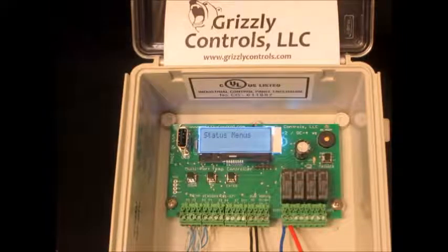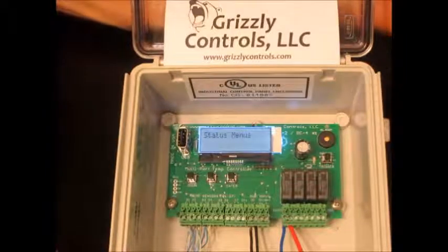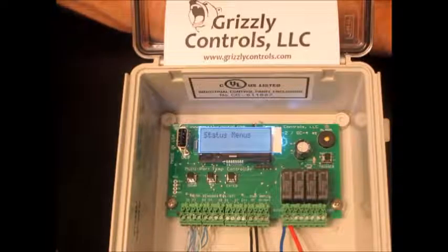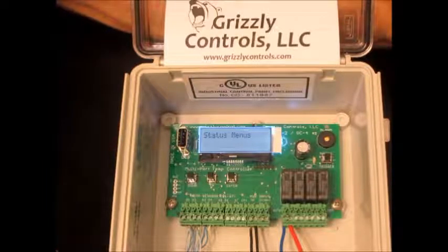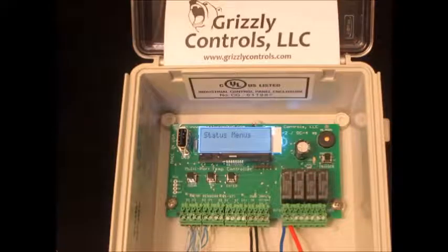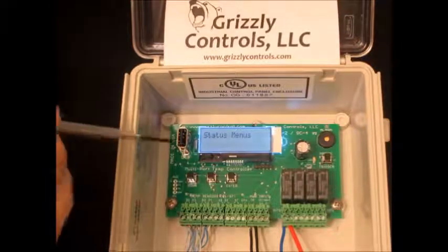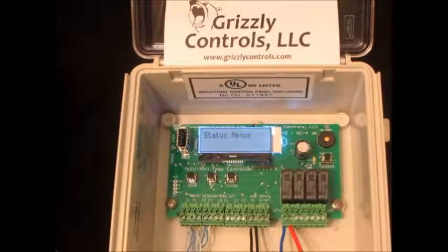There's an audible alarm here in the left corner. You can configure that to beep for whatever configurable output or control rule you assign it to. So if a certain control rule becomes active, it'll beep, or if an output becomes active, it'll beep, depending on how you want to configure it. On the left side, there's a USB interface. You use a straight cable. You don't need a USB to serial adapter or anything to connect to a PC.